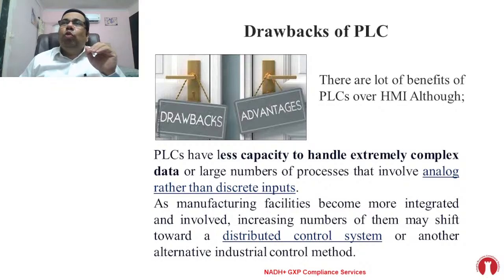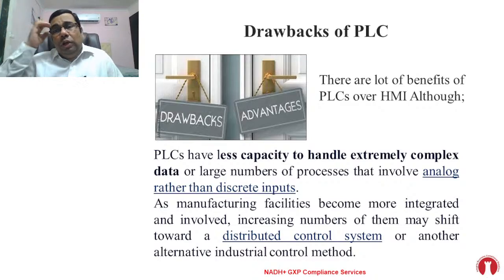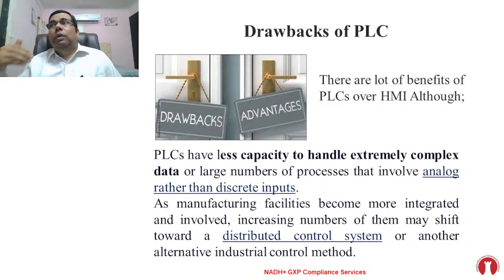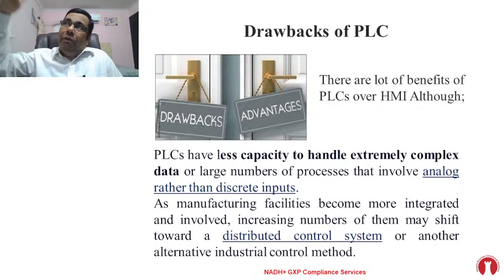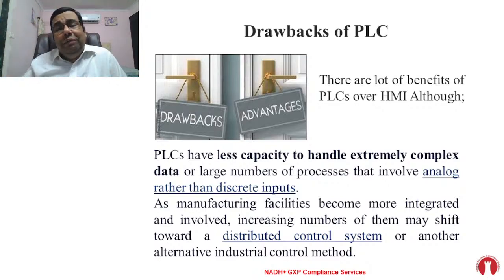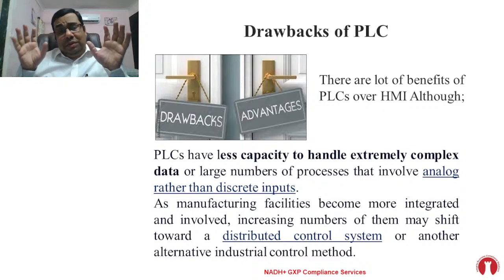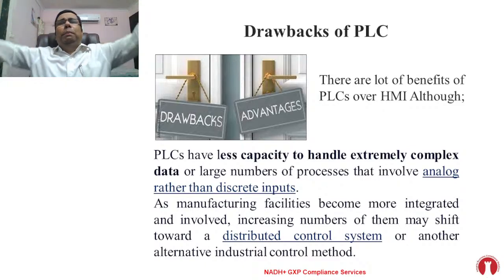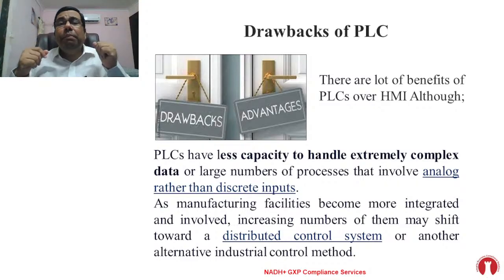In a water system, there are so many operating parameters. Based on operation parameters, there are some controls; some valves will open, some valves will close. There are separate cycles of sanitation, temperature controlling during sanitation. Simultaneously, during running operation, the velocity also needs to be maintained and all. So many parameters need to be maintained, right? At the same time, there is continuous monitoring of the level of the tank, then TOC or conductivity. So many parameters continuously we need to monitor. Now the point is this: if you think about it, there is a lot of data continuously because the water system is running continuously.